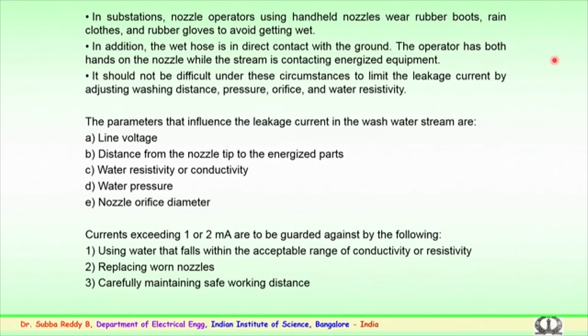In addition, the wet hose is in direct contact with the ground, and the operator has both hands on the nozzle while the stream is contacting energized equipment. So, it should not be difficult under these circumstances to limit the leakage current by adjusting the washing distance. So, the distance is very important, as are the pressure of the water spray, the orifice, that is the diameter of the nozzle set, and the water resistivity. Several of these things have to be adjusted to see that the person does not get contacted with the current or current flows through the body of the person.